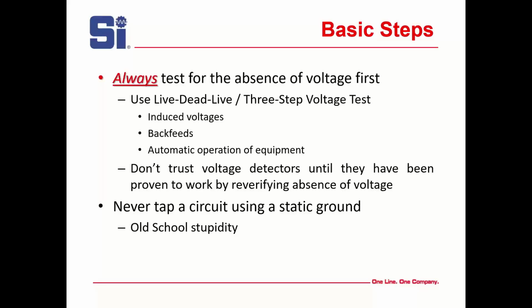Backfeeds. Seen this before where you get backfeeds on lines because somebody forgot to open a switch. And then automatic operation of the equipment by an automatic transfer switch. Those things have to be disabled. They have to be blocked out and locked out. Don't trust voltage detectors until they have been proven to work by re-verifying the absence of voltage. So you test live, you test the line to make sure it's dead, you test live, then as a last test, go back and recheck your line. Just a few seconds.